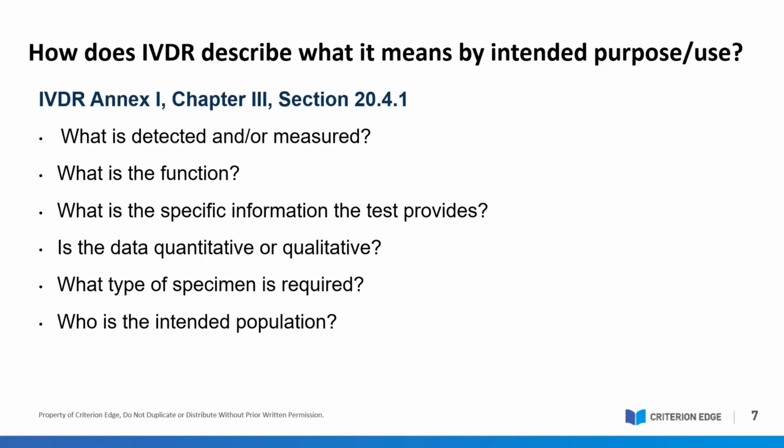And in our role as medical writers, we're often asked by our clients to help clarify what the difference is between a product's intended purpose and a product claim. So a device-specific intended purpose, as indicated in your IFU and in your labeling, serves as the basis for all product claims. IVDR Article 7 clearly states that the manufacturer is prohibited from misleading the user or the patient through a product claim about the device's intended purpose, safety, and performance.